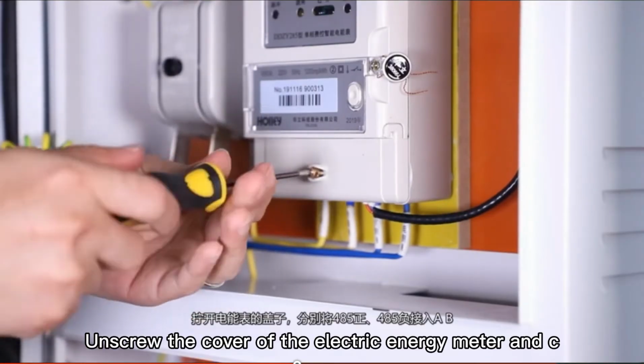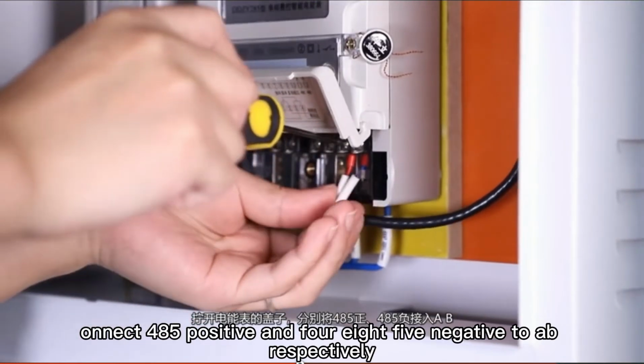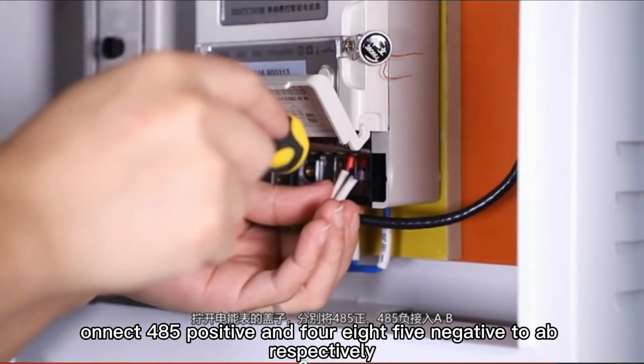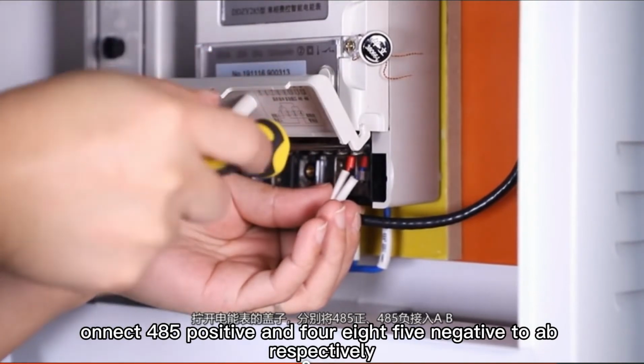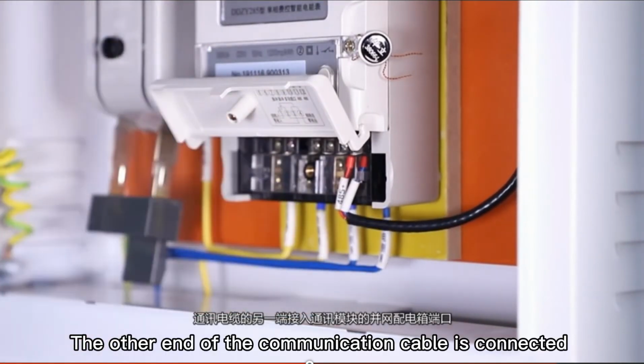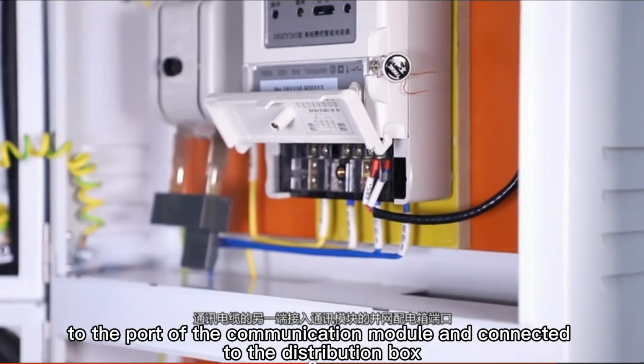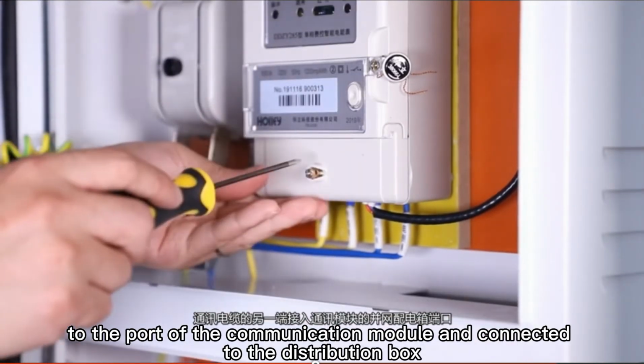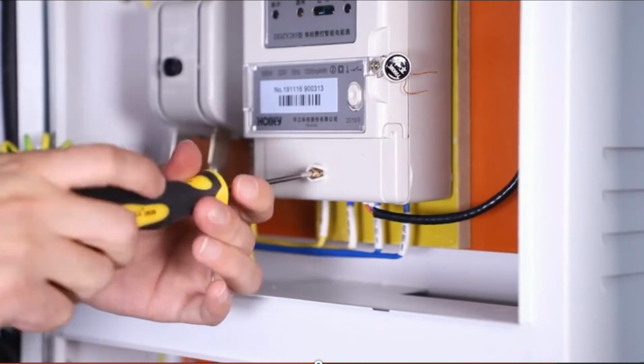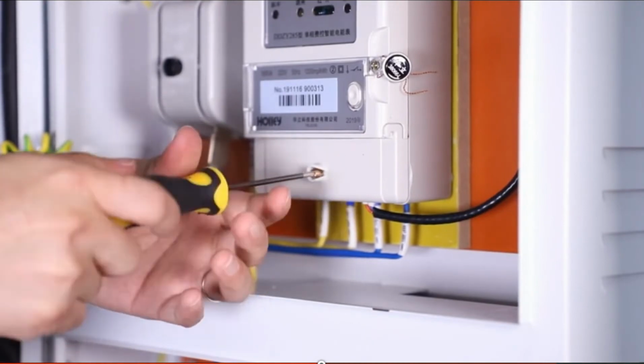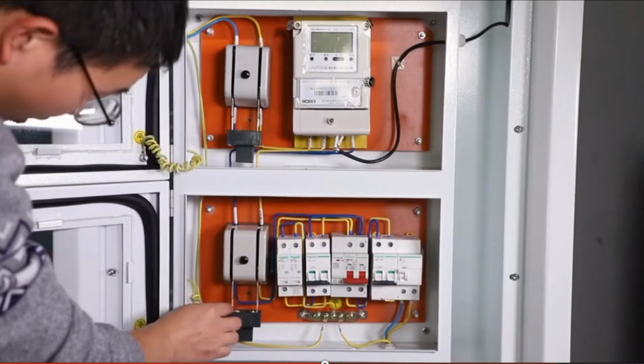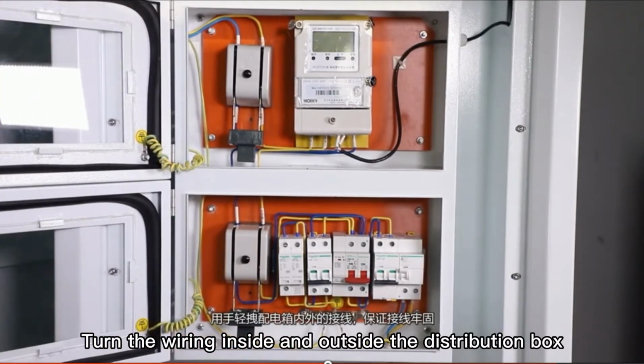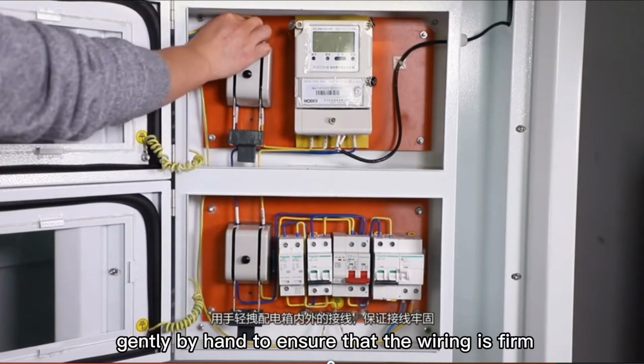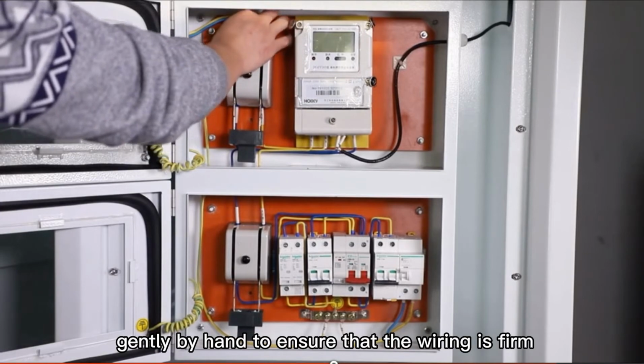Unscrew the cover of the electric energy meter and connect 485 positive and 485 negative to it respectively. The other end of the communication cable is connected to the communication module and connected to the distribution box. Turn the wiring inside and outside the distribution box gently by hand to ensure that the wiring is firm.